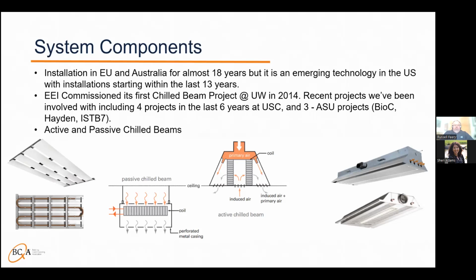We've got a few pictures here of active and passive chilled beams. On the left is a chilled sail that we used on a project, ISTB7, that we are currently commissioning. That design is fairly new. We had to go to Europe for some examples of it being installed, and the owner had some questions about maintenance, so there really weren't any installs in the US. Next to the right is a passive chilled beam, which includes basically a coil and is a convector type system. Then we move to an active chilled beam, where you've actually got some primary air and some coils. The pictures on the right are a couple of manufacturers' chilled beams.